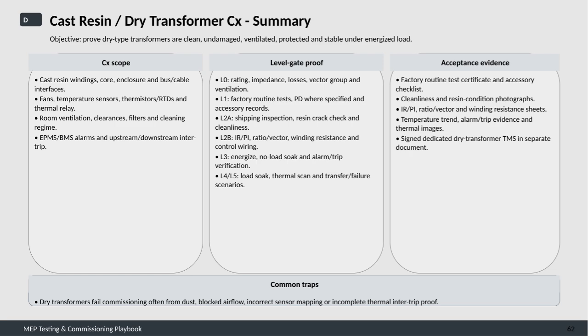The main objective here is to ensure that these transformers are clean, free of damage, properly ventilated, protected, and stable when energized under load. The commissioning scope covers several critical components. First, we verify the cast resin windings, the core, the enclosure, and the bus or cable interfaces. We also inspect the fans, temperature sensors, thermistors, RTDs, and thermal relays to confirm they're functioning correctly. Additionally, we assess room ventilation, clearances, filters, and a cleaning regimen to maintain optimal conditions. Finally, we check EPMS and BMS alarms and verify upstream and downstream inter-trip mechanisms to ensure safe operation.